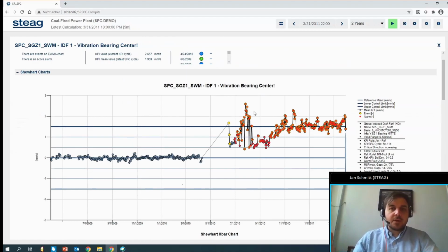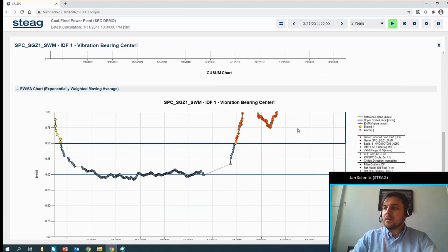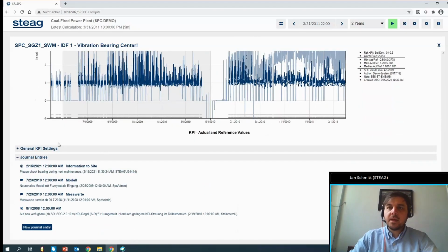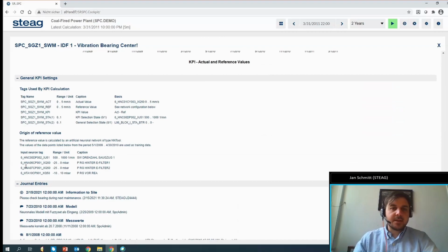Now we've seen the alarm, we have been notified, and we've verified that it's the first time it happened. The next thing we typically do is look at the input signals that are used to calculate the alarm. In this case, this can be rounds per minute, or a pressure before and after the fan, basically physical signals going into the calculation.